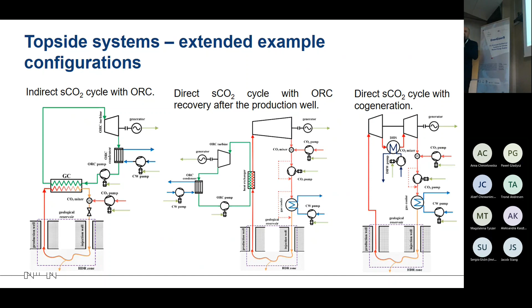We also looked at designs that allow us to split the turbines and have a cogeneration system, varying the temperature parameters to meet the requirements for different generations of district heating systems. We're talking about third generation, which is mostly common in Poland, but also looking at fourth generation with much lower temperature requirements. Here is a study, this time for Polish conditions.